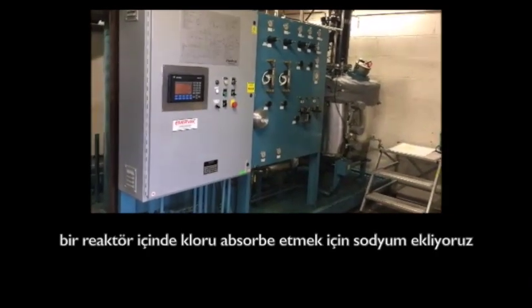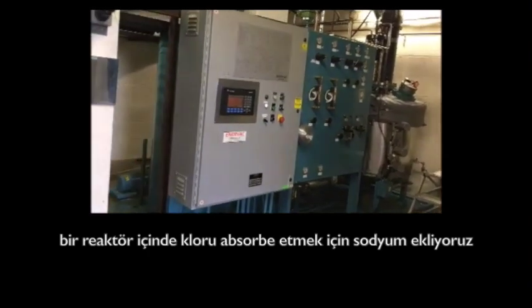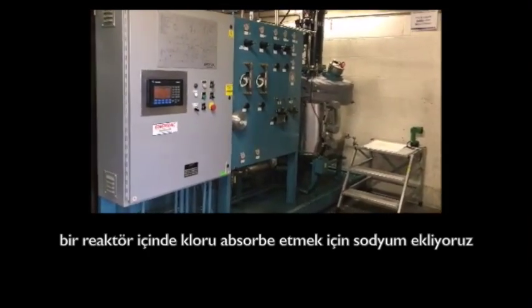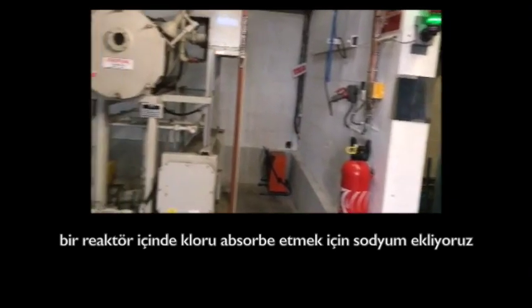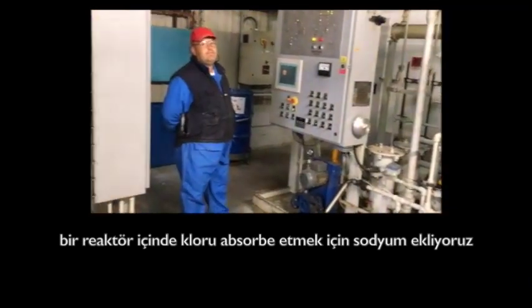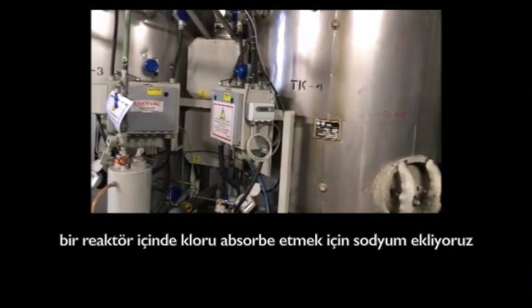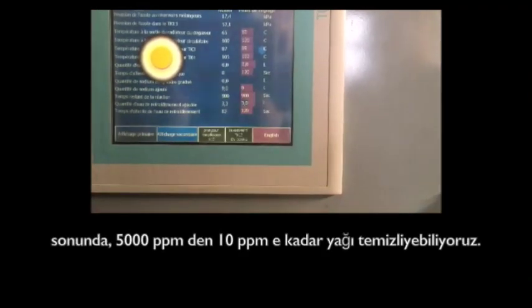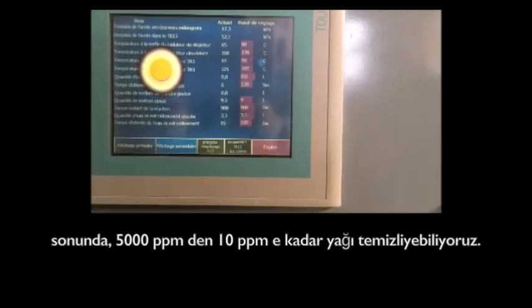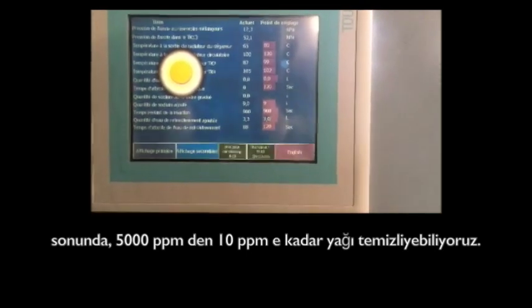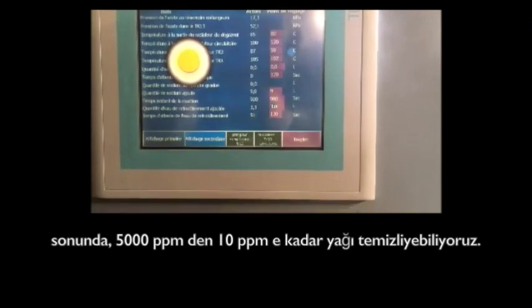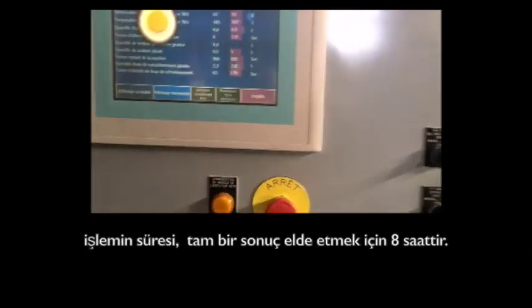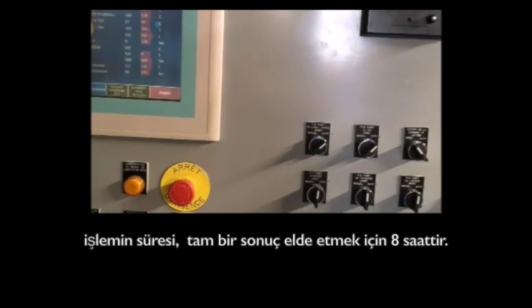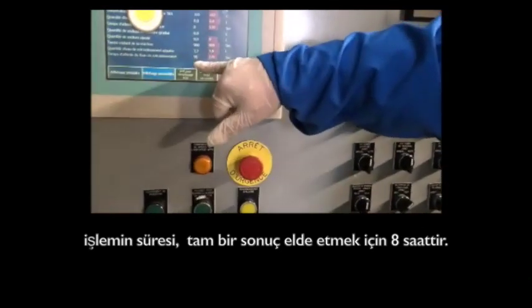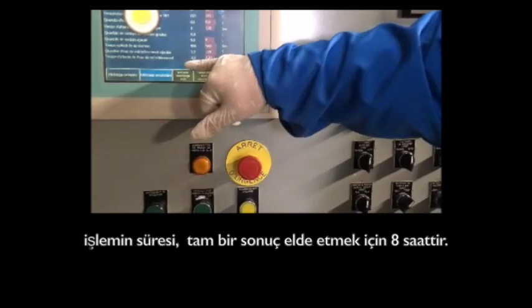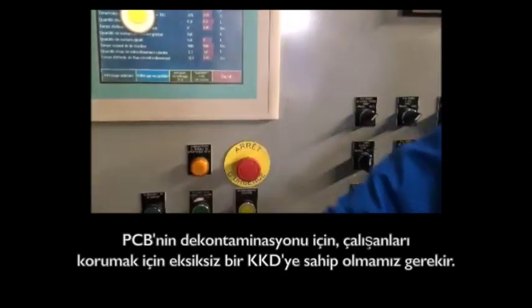We add some salt to separate the chlorine and to reduce the chlorine in the oil, and at the end we can refurbish the oil by this system from around 5,000 ppm to 10 ppm. It very much depends on the time, but the duration is around 8 hours for the complete process.